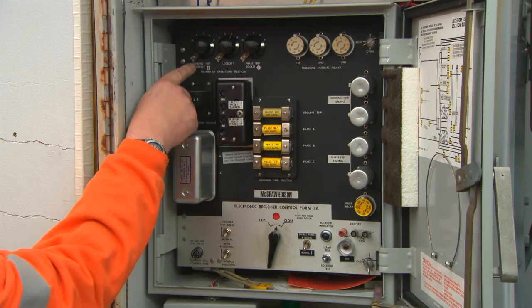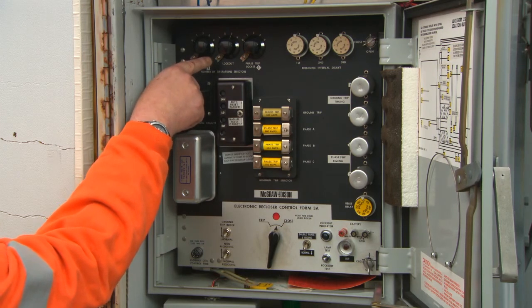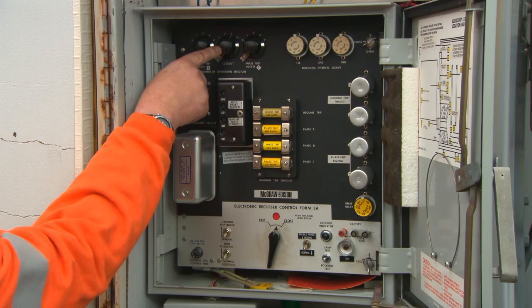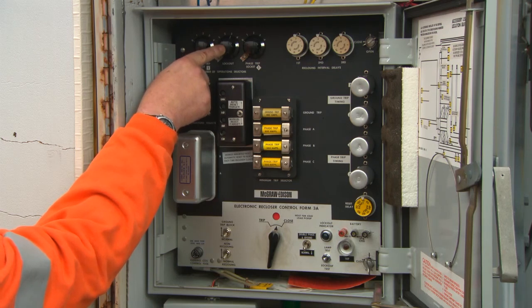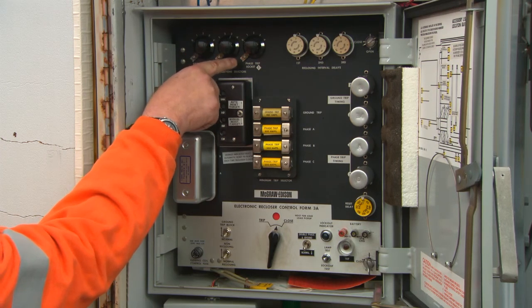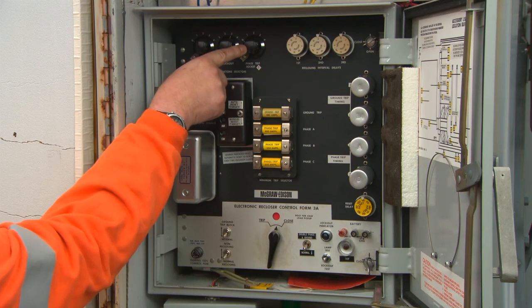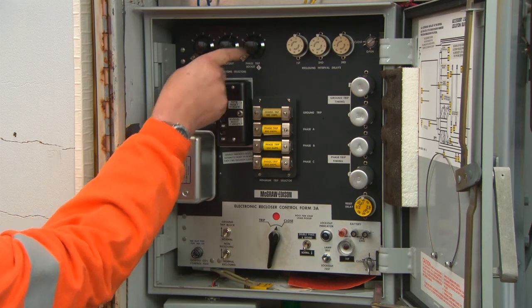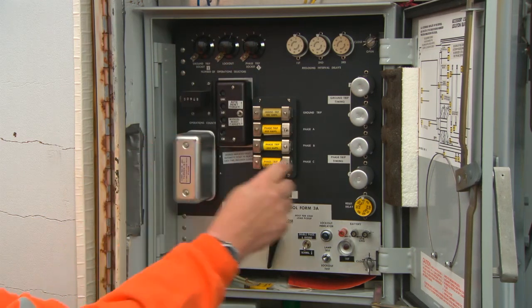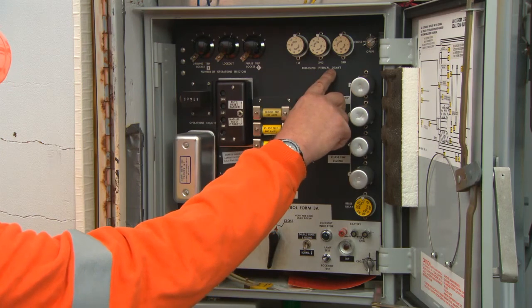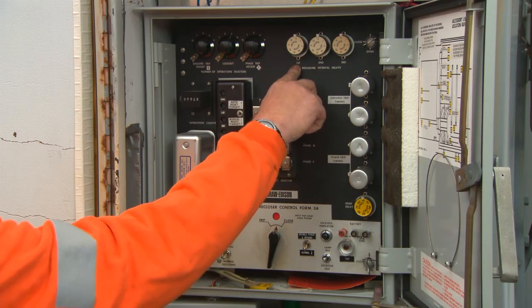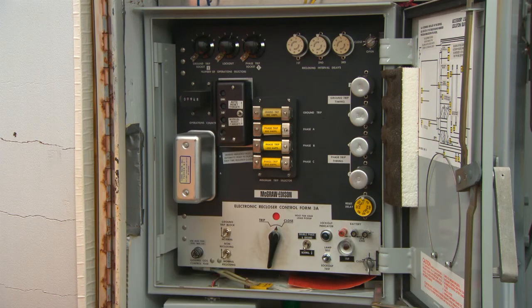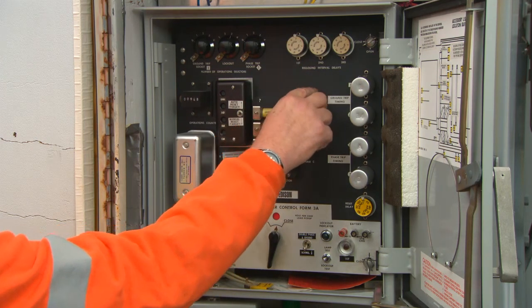On this unit, it is set to 0. The center rotary knob is used to set the total number of operations to lockout. This unit is set for 3. Phase Fast Trip programs the number of fast phase trip operations as defined by the plug in socket 1. The remaining slower operations are defined by the plug in the phase trip socket 2. The unit is set to 0.